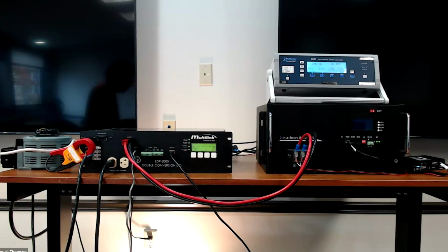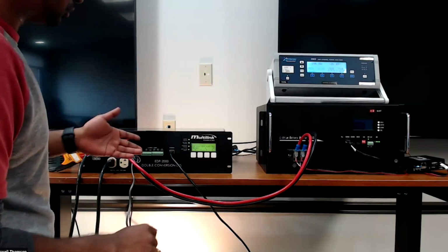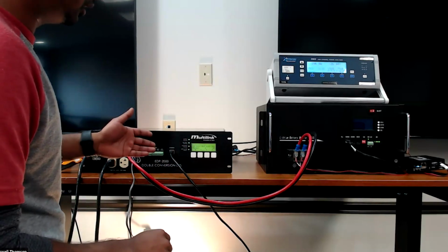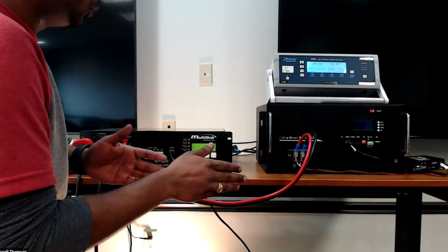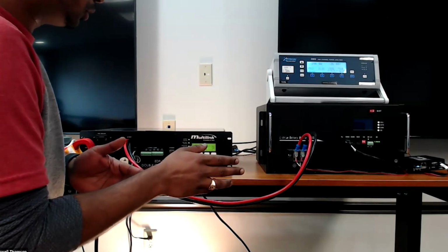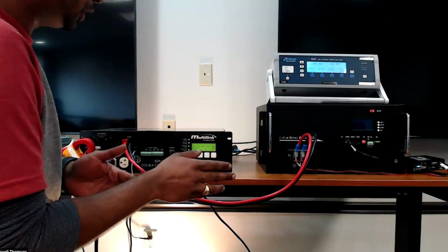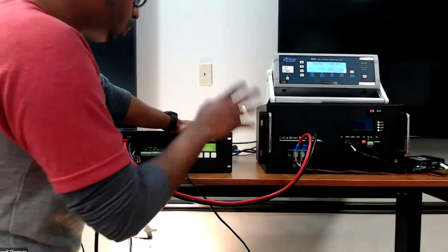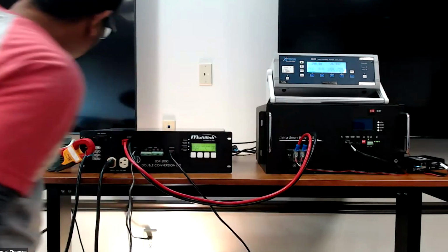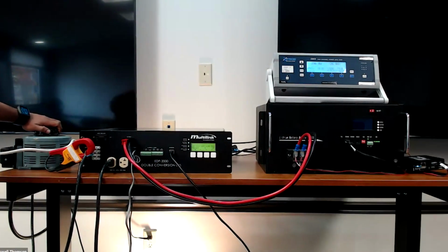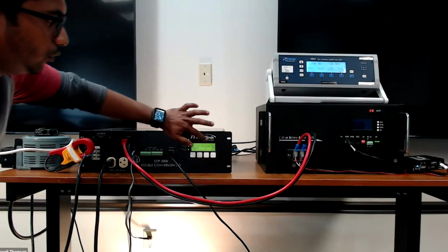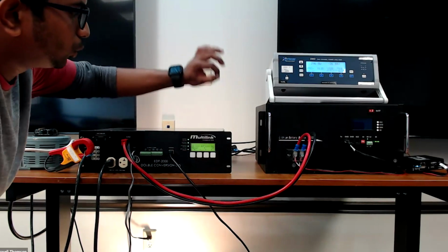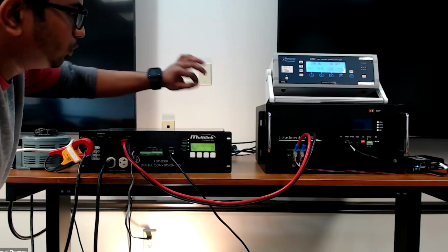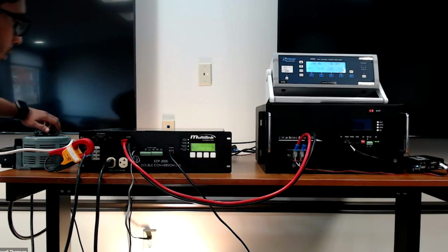And you can see the clamp which reads the input current. Let's start the operation of checking the inverter mode. As I said earlier, it's doing a double conversion where it won't convert the AC into output current, output voltage, where it gets power only from battery. Let me crank the AC to 0 so you can see we'll be getting a continuous 120 voltage all the time, even with the AC failure.